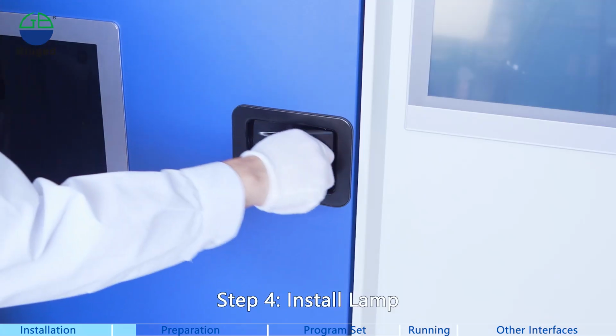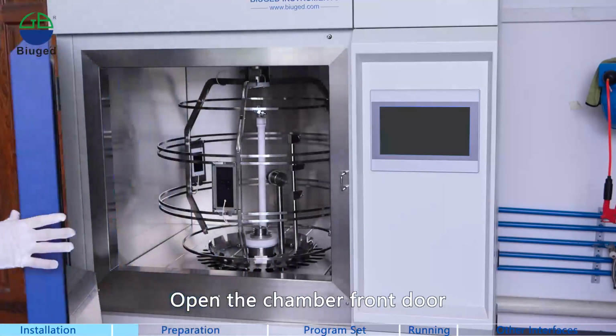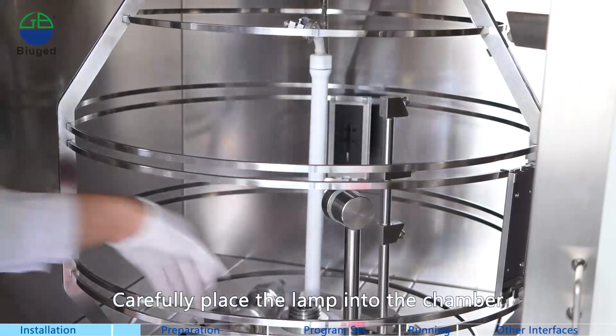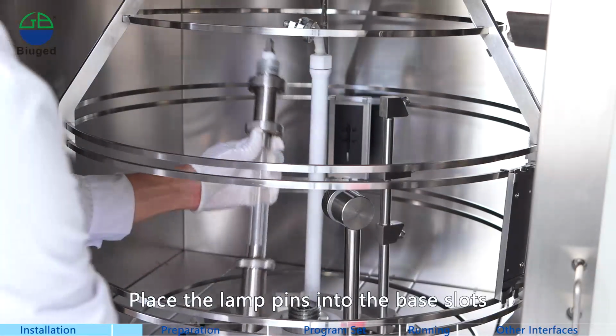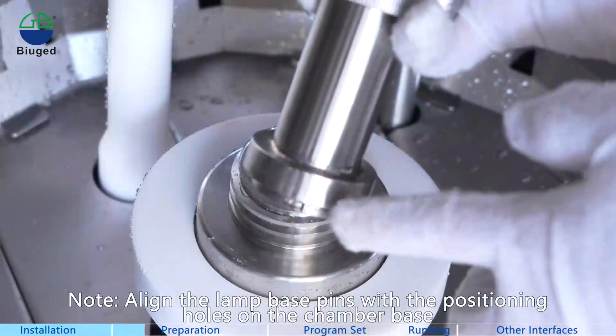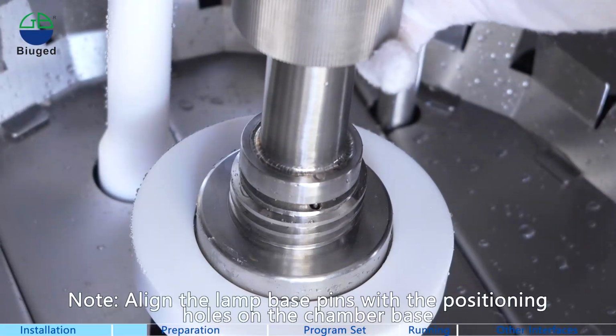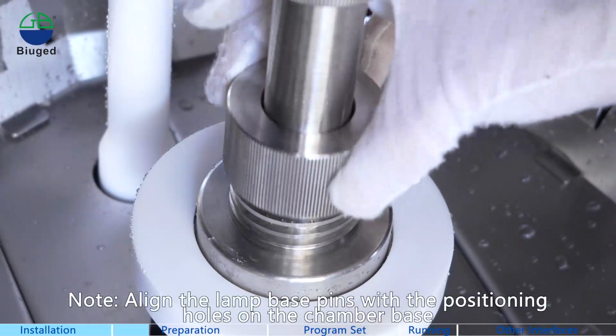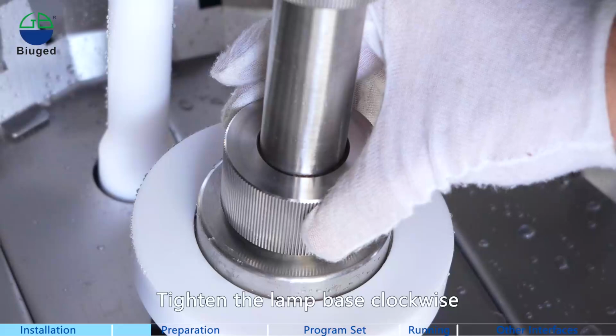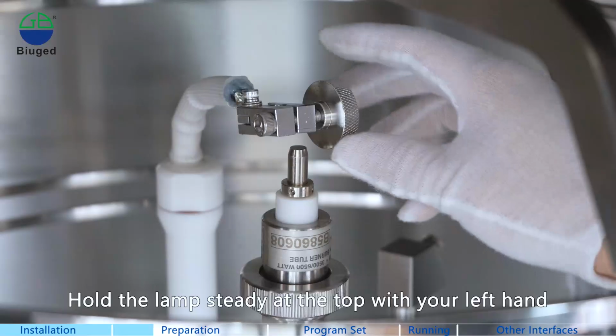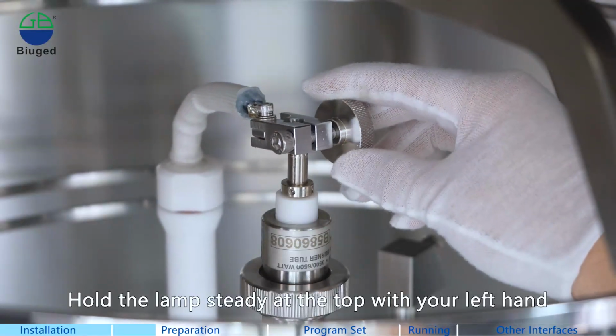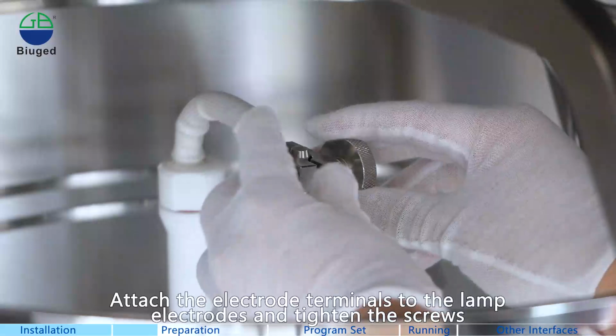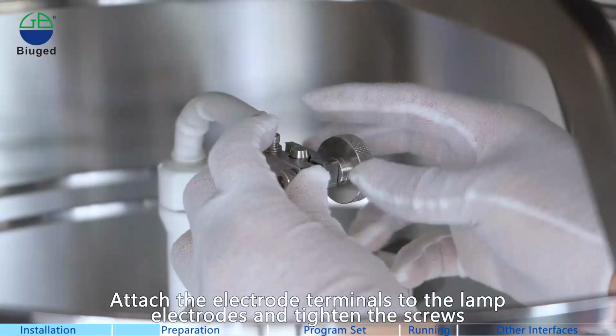Step 4. Install lamp. Open the chamber front door. Carefully place the lamp into the chamber. Place the lamp pins into the base slots. Note: align the lamp base pins with the positioning holes on the chamber base. Tighten the lamp base clockwise. Hold the lamp steady at the top with your left hand. Attach the electrode terminals to the lamp electrodes and tighten the screws.